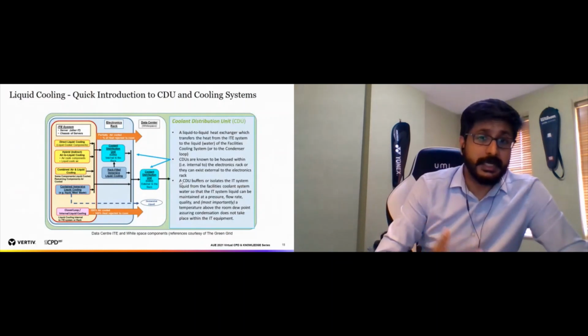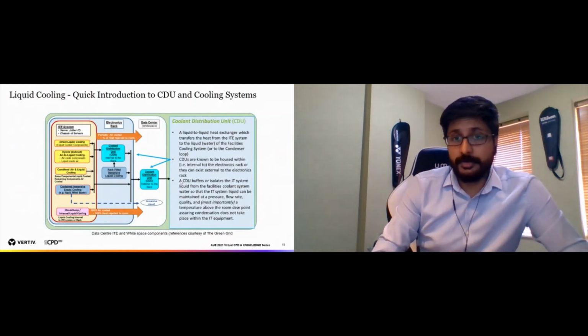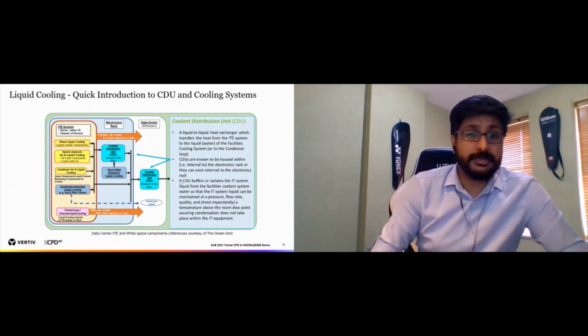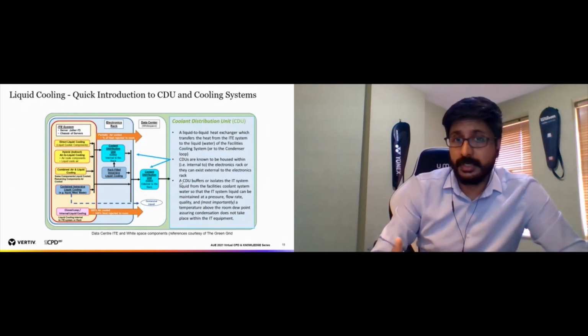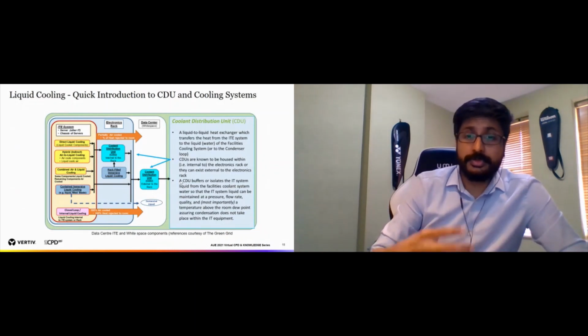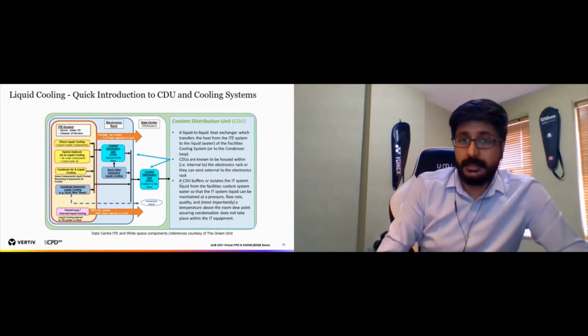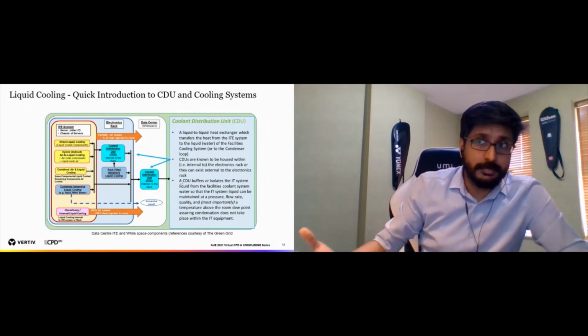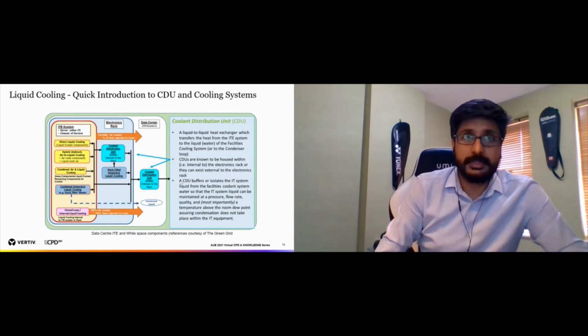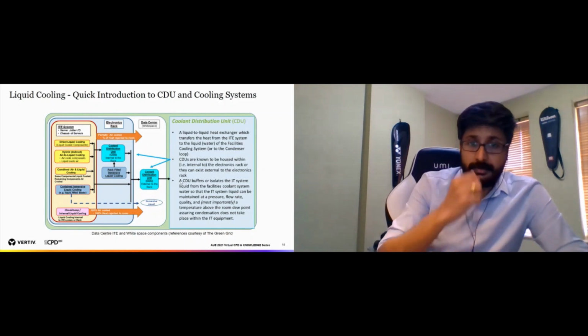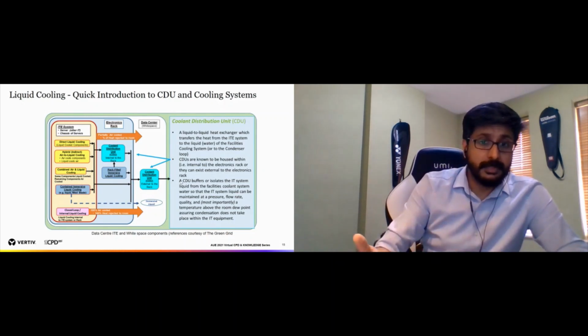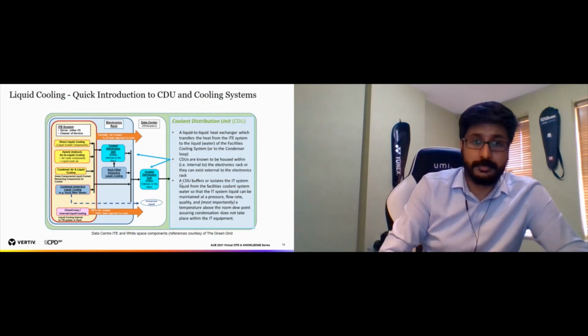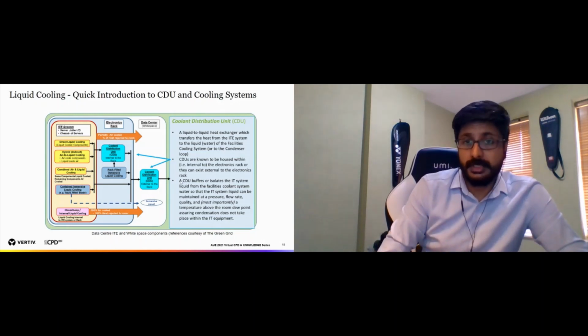It can be direct liquid cooling, where there's a chip cooling element in there. Then there's a hybrid option where the components are liquid cooled, or use, for example, a cooled fan, and then the fan just blows cold air into the servers. Then there are combined air and liquid cooling solutions, where you can have a rear door cooling and, at the same time, chip cooling as well. And there's a fully immersed, or fully immersion, cooling option as well.